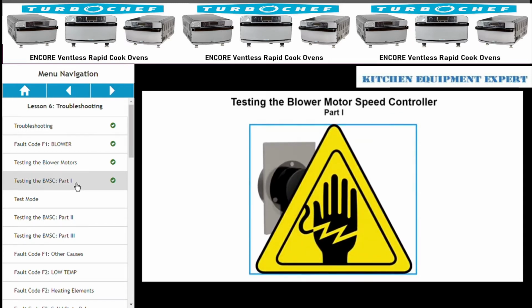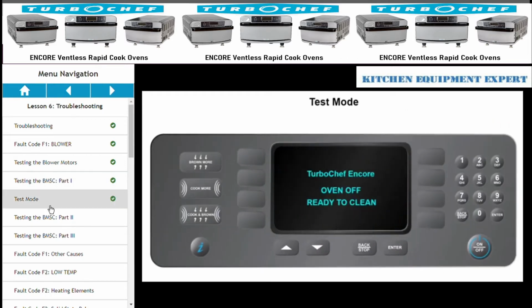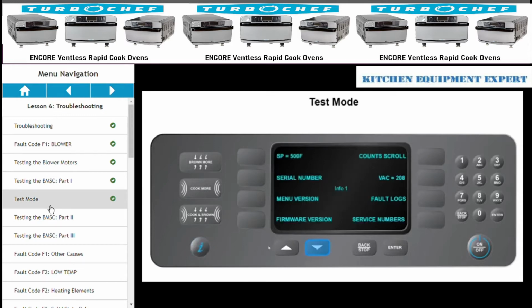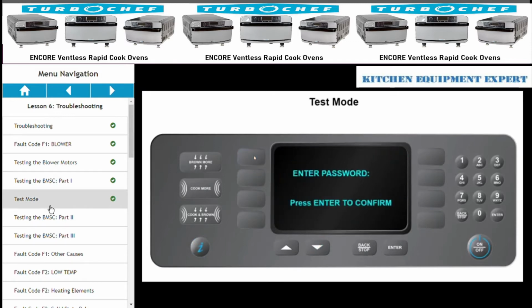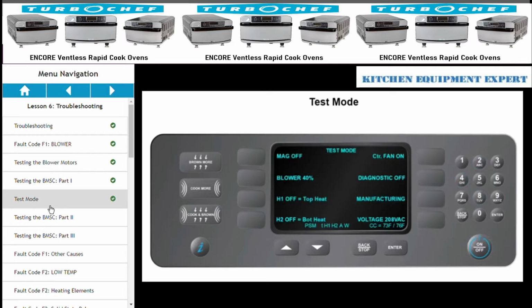The next test requires using the test mode. To enter the test mode, first press the info button. Press the down arrow to move to the second screen. Press the soft key next to test mode. Enter the password, 94288. You're now in the test mode.